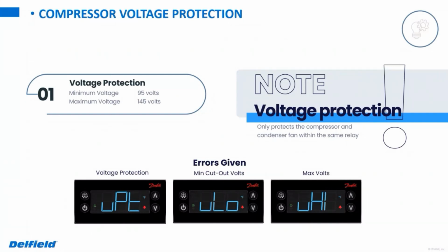So anytime you see a ULO or UHI showing on the display, that means the voltage is too high or too low. You can check it at the wall outlet. We've actually seen this as a failure mode as well, where it's showing high voltage. We check the voltage at the wall outlet, it's 120 volts. If that's the case, we would just have you replace the control at that point. But normally it would show a variation in that voltage.